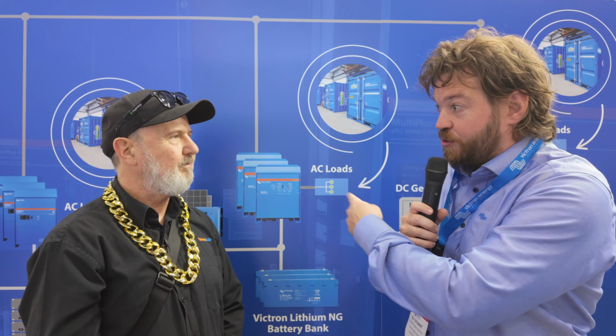So you've solved the current problem too. You can have independent battery banks. The DC bus no longer needs to be connected or synchronized. Each system is independent unto itself. You could have a lead acid battery bank, a legacy system that you don't want to touch, but it can still feed into this system from a MultiPlus. You can add a lithium battery bank to it and feed it all through to the same AC.